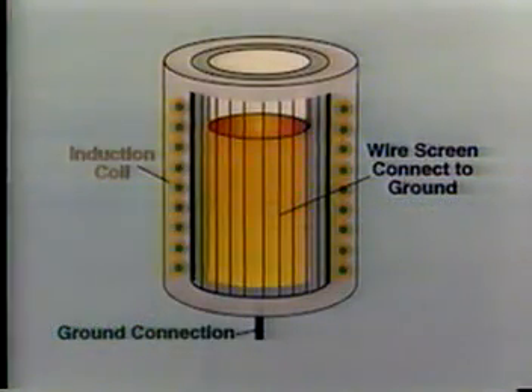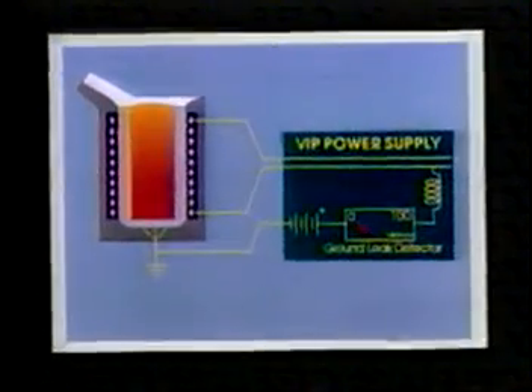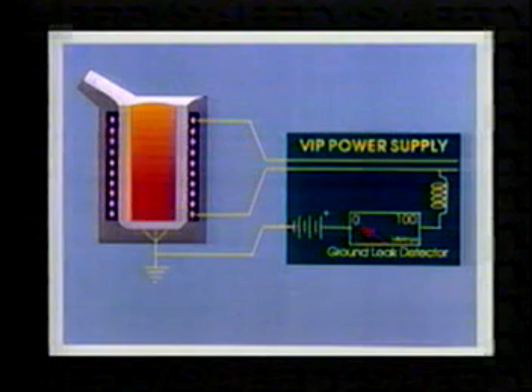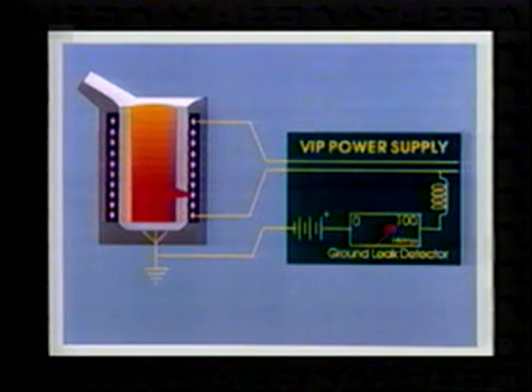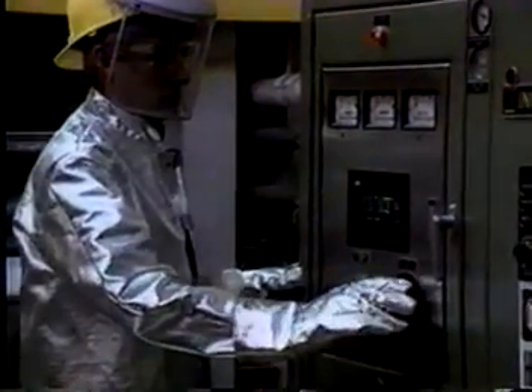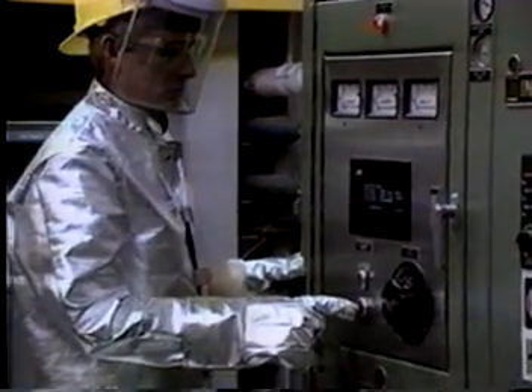In some small furnaces with non-conductive, non-removable crucibles, where the bath cannot be practically grounded, the ground leak detector probe may take the form of a wire cage located between the crucible and coil. This wire cage serves to ground the bath if metal penetrates through the crucible. Both of these probe configurations provide shock protection to melt deck workers by assuring that there is no voltage potential in the molten bath. If molten metal were to touch the coil, the ground leak detector probe would conduct current from the coil to ground. This would be detected by the ground detector module, and the power would be shut off to stop any coil arcing. As a normal safety precaution, power to the furnace always should be turned off during slagging, sampling, and measuring.